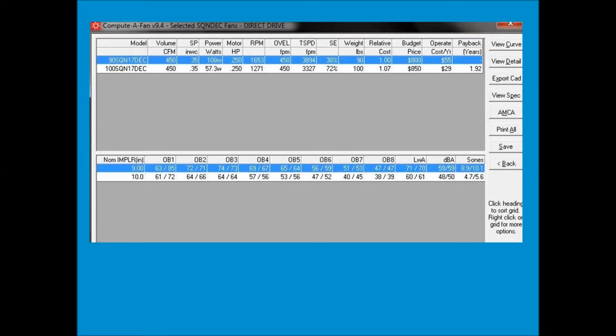Now these ones here are belt drive fans — a small little square inline fan. I would suggest that if we went instead with a direct drive fan, here's a couple of options: a size 90 or a size 100. In both cases, the RPM is really good, horsepower is low, sound is low. And as we discussed in our previous segment, being direct drive, it's less expensive, it's easier to control, and the maintenance is minimal compared to a belt drive fan.